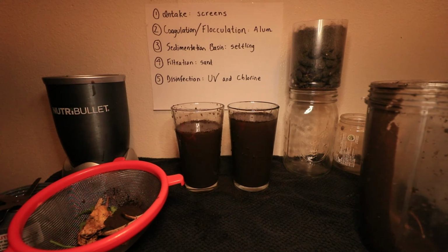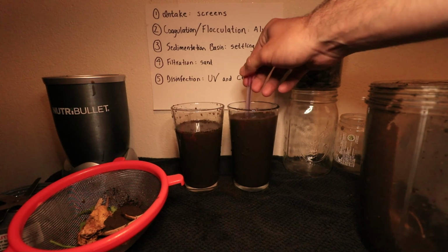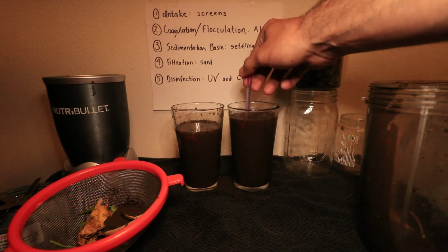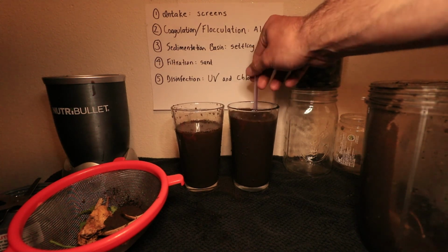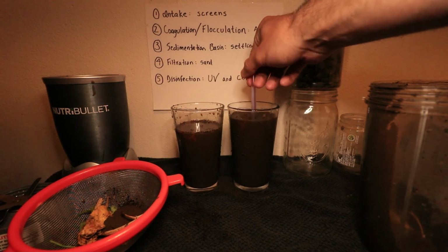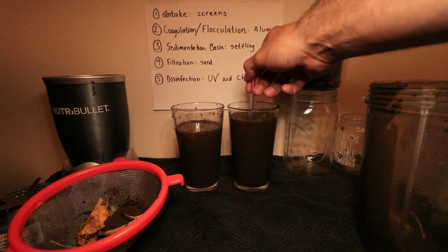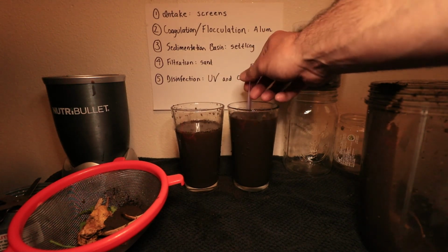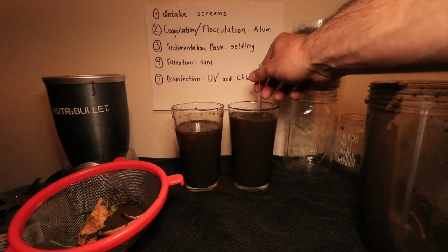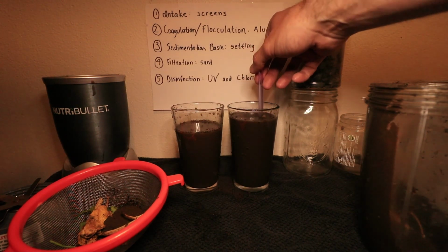I'm going to go ahead and give that a good stir. The amount of alum that is added is a little bit more strategic than what I just demonstrated. They've got their ratios a little bit more dialed. And when it's first added, it's mixed pretty rapidly during the coagulation process to get it to distribute throughout the sample. And then it moves into the flocculation, I have a hard time saying that word, area. And that's where the mixing is a little bit more controlled.